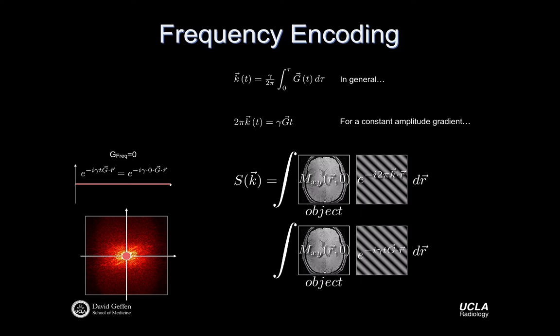So we can think about the simplest example, right? When we're right in the middle of k-space, our frequency encoding gradient is just zero. At that point in time, maybe I haven't turned anything on. I don't need to turn anything on. I've prepared my spin system with some form of contrast, I've generated some transverse magnetization, and I just turn on my receiver.